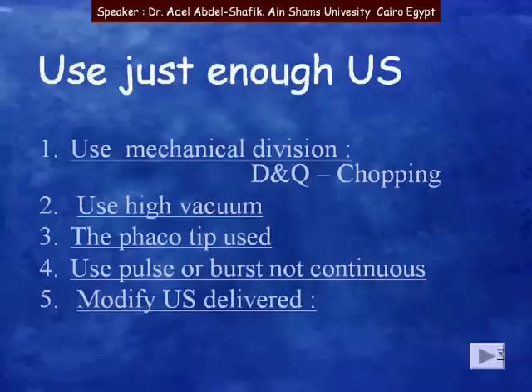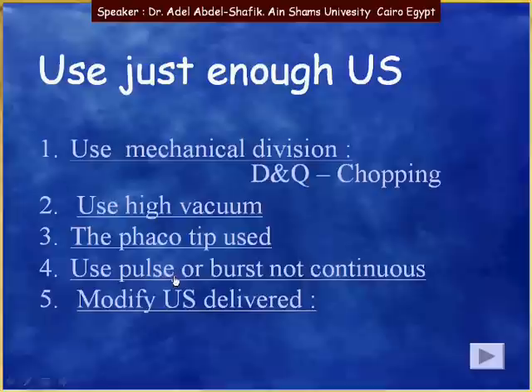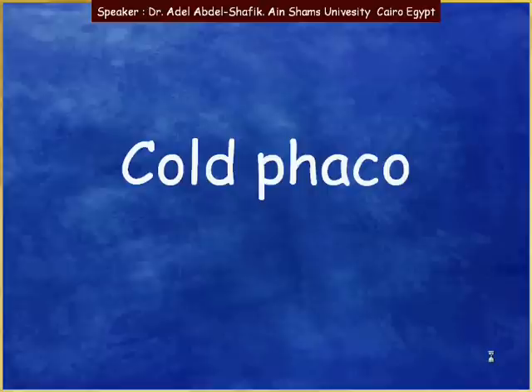In summary, you can reduce the amount of ultrasound by using mechanical methods like division or chopping, by using high vacuum to mechanically remove material, by changing the tip to apply ultrasound more efficiently, by using pulses or bursts instead of continuous mode, or by modifying the ultrasound duty cycle in some of the newer machines.